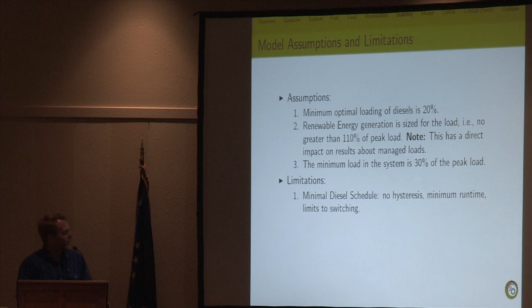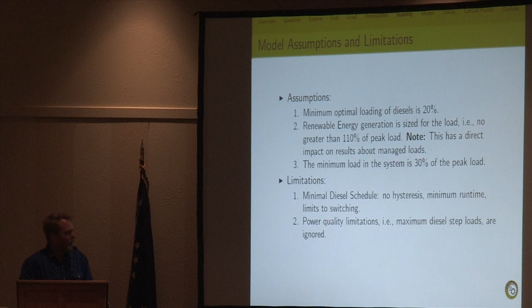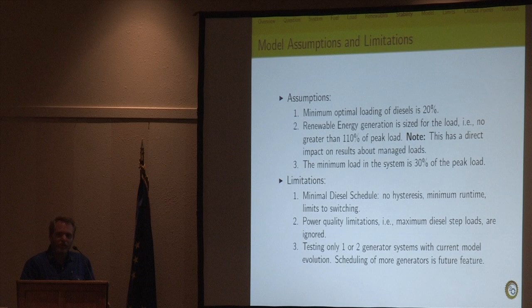And then we have limitations to this model. This is a rather theoretical study at this point, but it informs a few things. There's no hysteresis in the system, no minimum runtime on the diesel. So we're reducing the complexity of what is diesel scheduling. We're not considering power quality issues at this point, because we're just running an energy balance model. And we're only running 1 or 2 diesel generators.